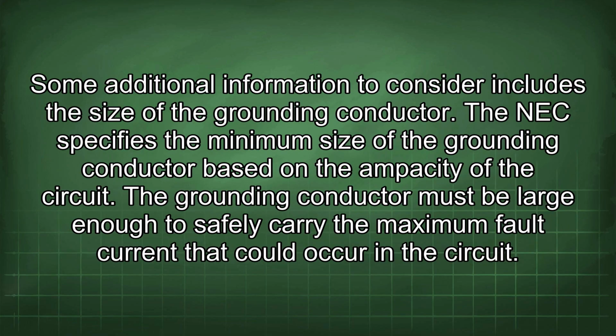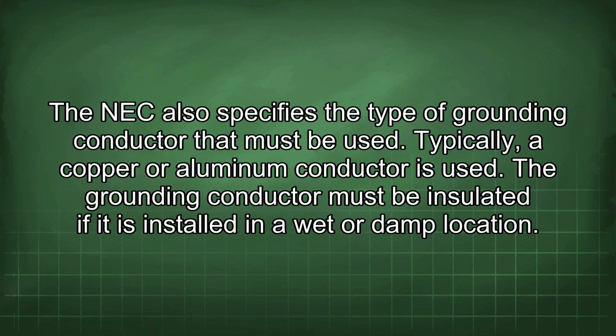Some additional information to consider includes the size of the grounding conductor. The NEC specifies the minimum size of the grounding conductor based on the ampacity of the circuit. The grounding conductor must be large enough to safely carry the maximum fault current that could occur in the circuit. The NEC also specifies the type of grounding conductor that must be used. Typically, a copper or aluminum conductor is used. The grounding conductor must be insulated if it is installed in a wet or damp location.